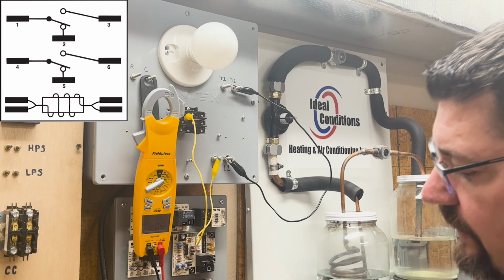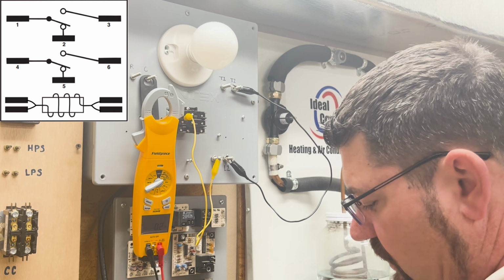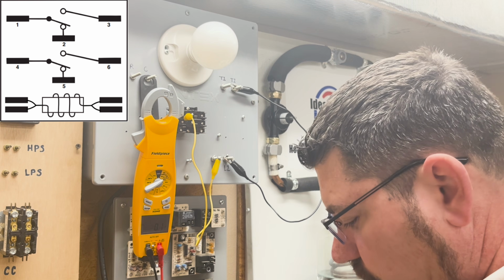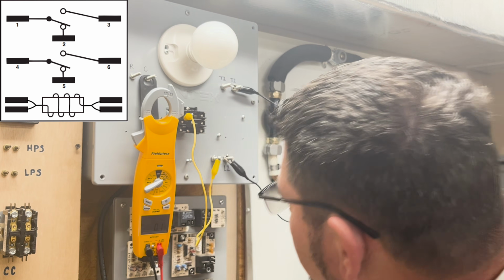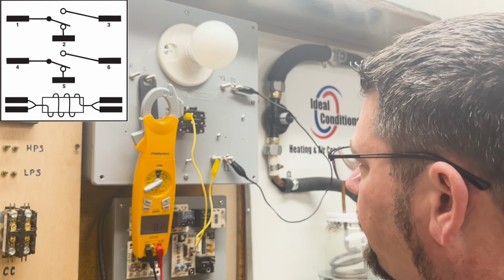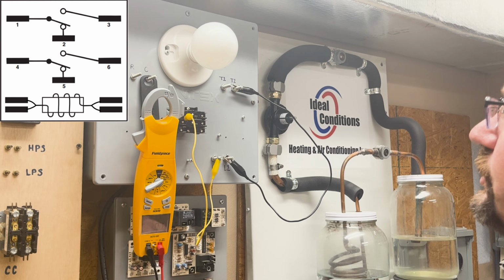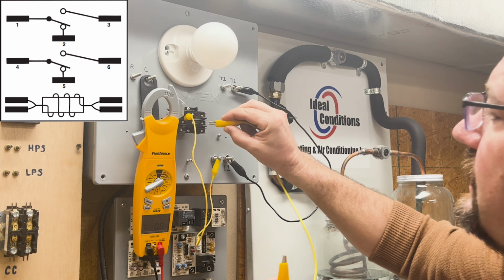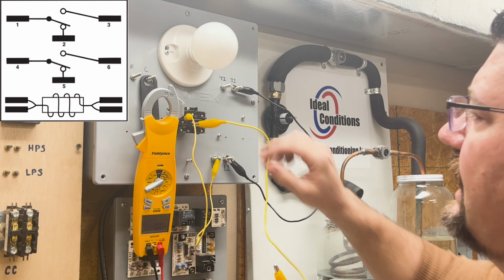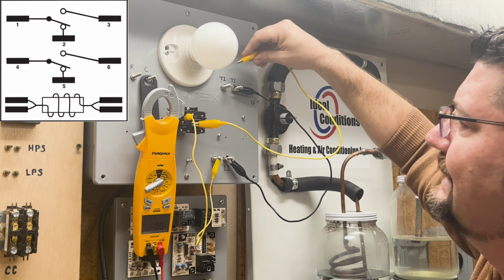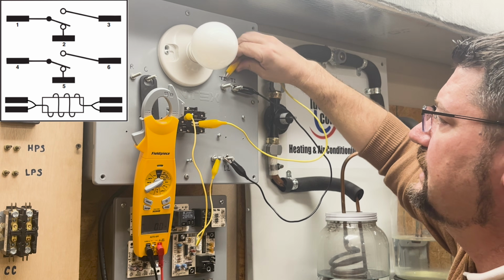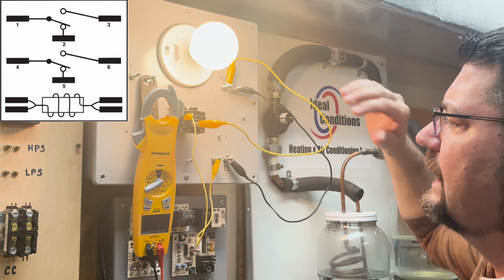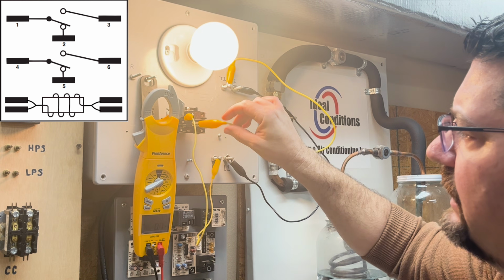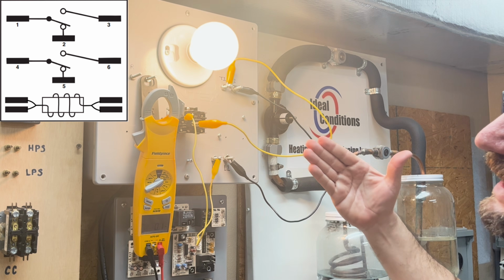I'm going to go ahead and leave it on that pole for a second here. And I'm going to show you that if I were to come out of terminal 5 up to terminal 1, the light will come on because we'll be providing it the second leg of power that it needs. So we're going to go ahead and wire it up to T1, and the light came on. And so I didn't need 24 volts to make that happen.